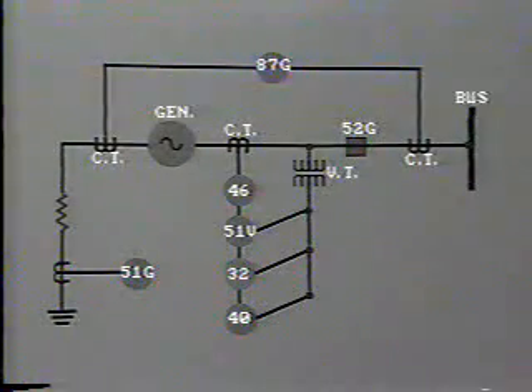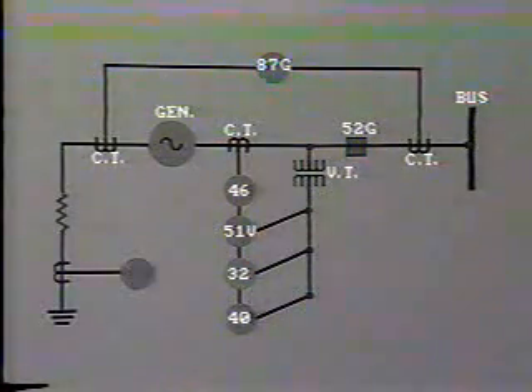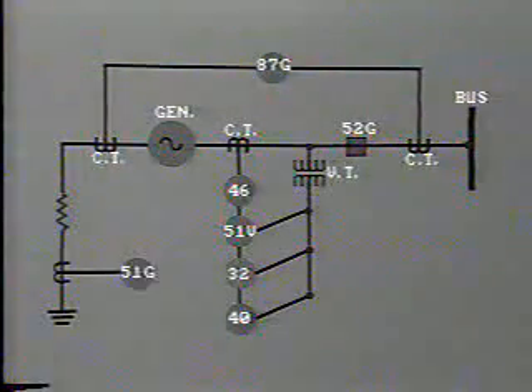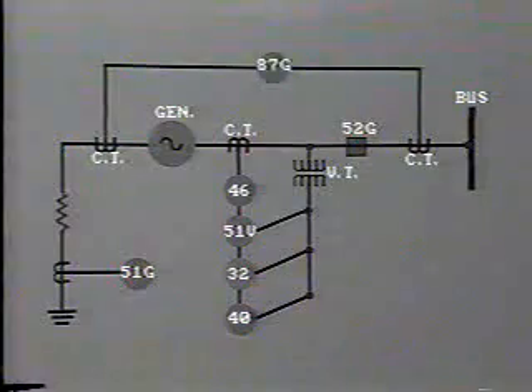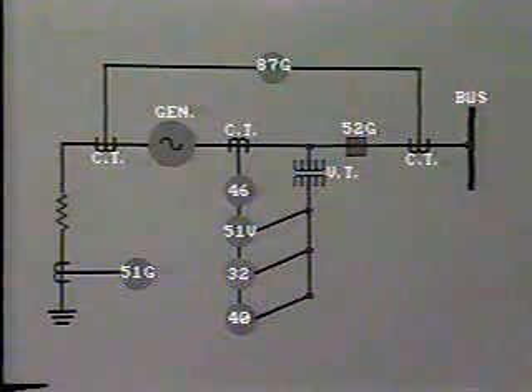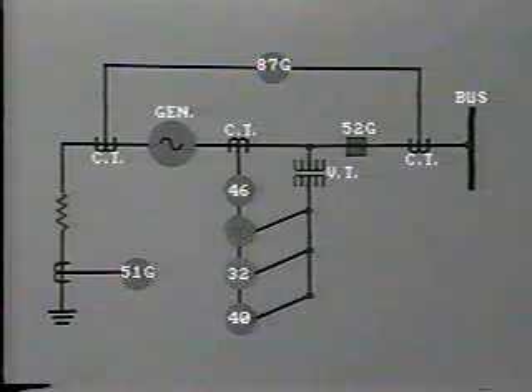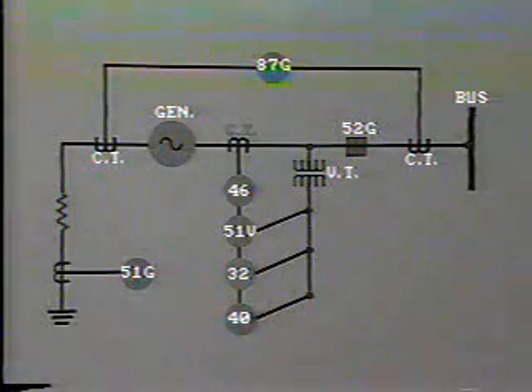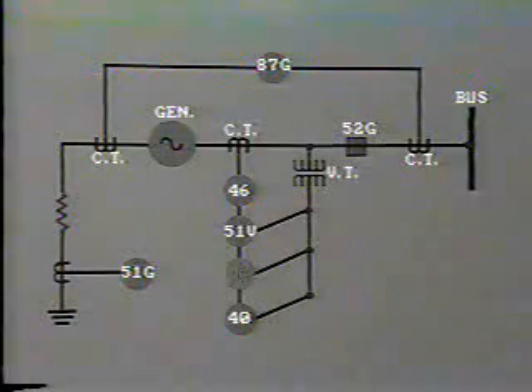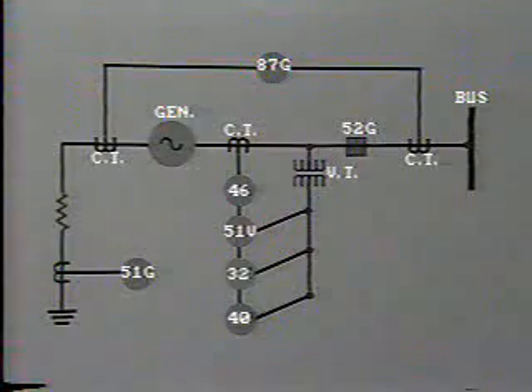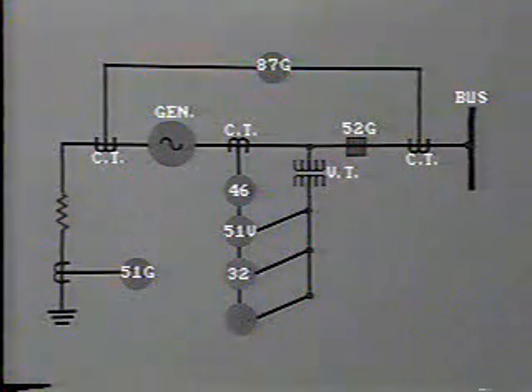A generator connected directly to a bus through circuit breaker 52G. You can already recognize some of these device numbers. 51G is a time overcurrent relay in the neutral to ground. 87G, a differential relay across the generator. What is this 46? A negative phase sequence relay. 51V is a voltage restrained time overcurrent relay fed by the CT in the generator output, and a voltage transformer which also feeds a directional power relay, 32, and a loss of field relay, 40.